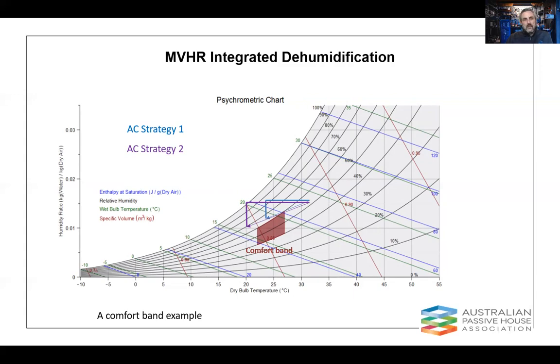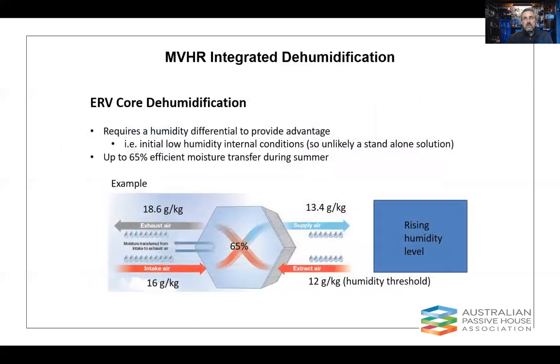What we can see is using the AC unit on its own, we can cool, but we can't get the temperature and the humidity correct at the same time. So we end up right temperature, but still sticky, or too cold once the humidity is in the right area. So what can we do to solve this? Well, the first simplest part to that is ERV core, or enthalpy type cores.